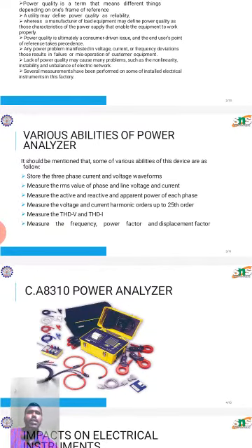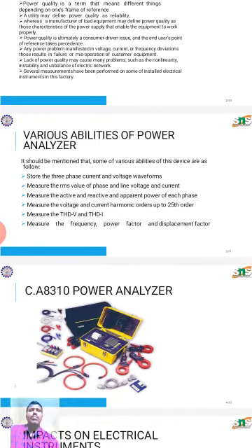Next, various abilities of the power analyzer. The CA8310 power analyzer has been shown in the given figure. Some of the various abilities of this device are as follows. First, store the three phase current and voltage waveforms. Second, measure the RMS value of phase and line voltage and current. Third, measure the active, reactive and apparent power of each phase. Fourth, measure the voltage and current harmonic orders up to the 25th order. Fifth, measure the THD-V and THD-I. And last, measure the frequency, power factor and displacement factor.